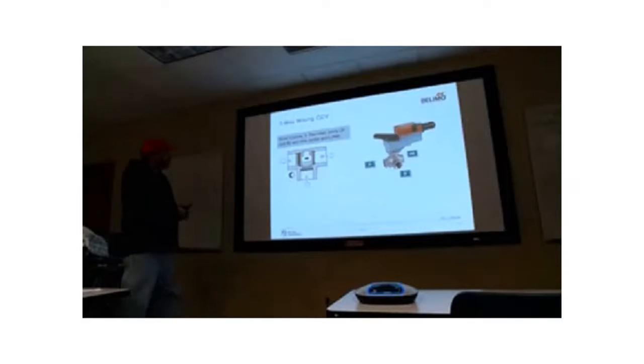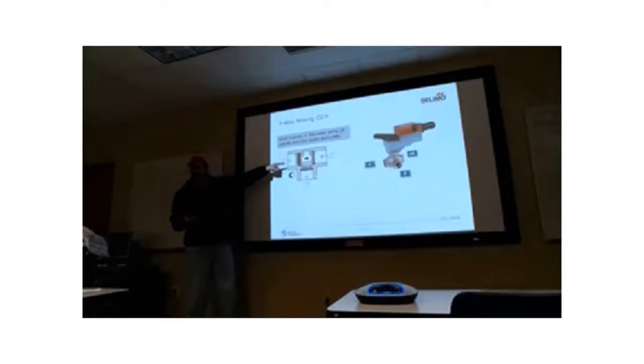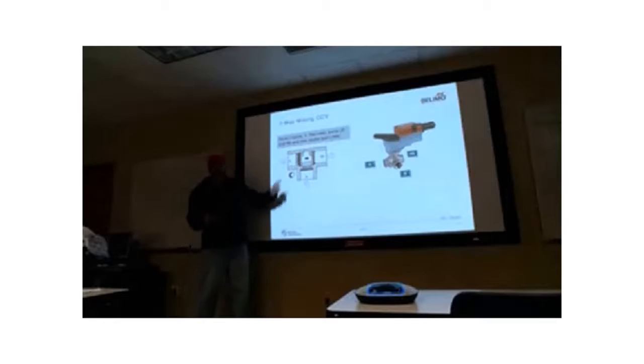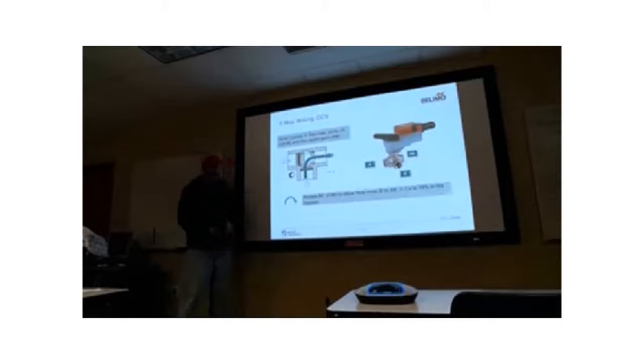But if you don't, what will happen is the actuator might get out of sync in terms of the way this valve is supposed to operate. There are only 2 acceptable positions, endpoints for this valve as it sits right now, and one of them is this. You're going to see the slots where you're going to have one slot here, one slot here, and one slot here, and the B port's going to be down here. This is what we call open A to AB. The other acceptable position is 90 degrees rotation clockwise, right? So now we're going to close the A to AB port, and now we're going to open the B to AB path, right? Now, there's 2 more positions of this valve, aren't there?